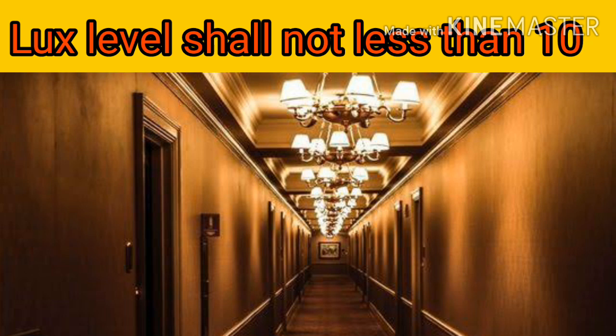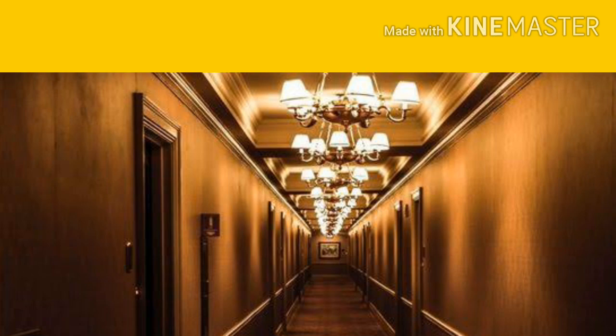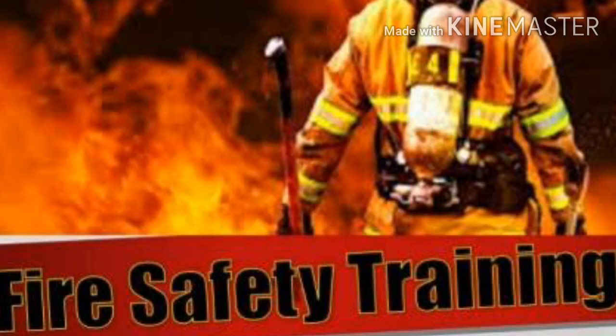Emergency power supply and lighting is very important. A standby power supply shall be provided in a hotel to cater for emergency in the event of failure of normal power supply. Such standby power supply shall be independent and through a diesel generator of adequate capacity to meet the following minimum requirements: emergency illumination of all corridors, staircases, basements and exit signages, and fire lifts, and mechanical ventilation for basements or in case of a centrally air conditioned building, and fire water pump. However, if a standby diesel pump is provided, this may be exempted, and other emergency automatic systems for firefighting also.